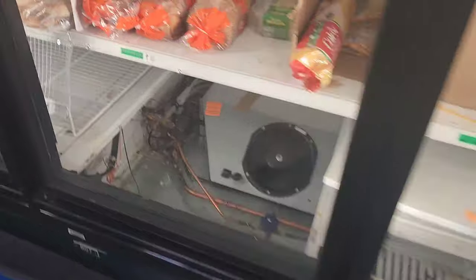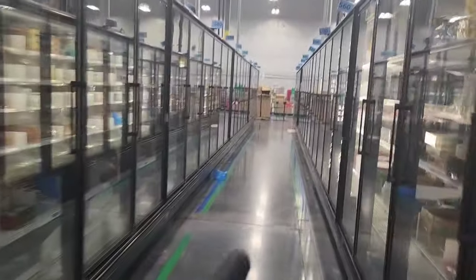Cases are stocked at temperature — how do you find a freaking leak here? What I did was at the break of each case, that's where you've got your TXVs and your piping that goes in. So I just opened up each one on those ends and I got lucky. I'm gonna show you where I got lucky. There are three aisles like this — we've got like eight rows of this. It's insane.